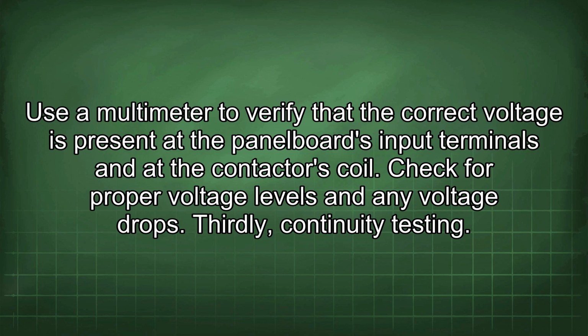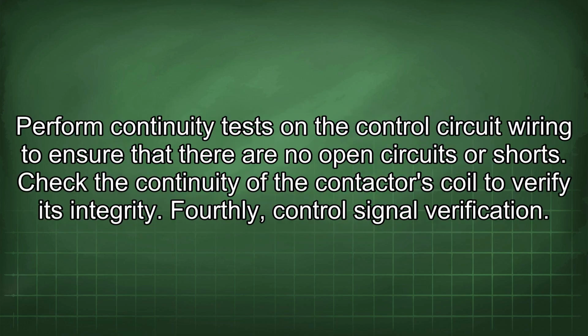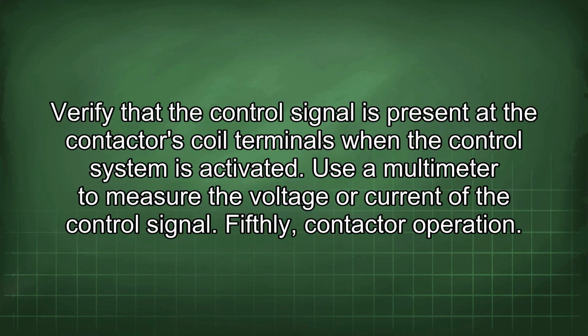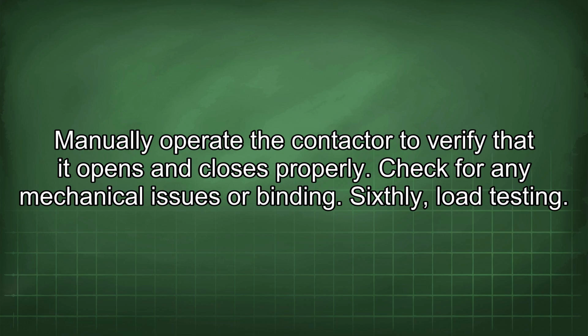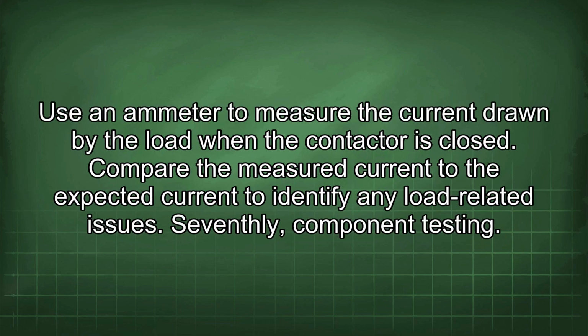Thirdly, continuity testing. Perform continuity tests on the control circuit wiring to ensure that there are no open circuits or shorts. Check the continuity of the contactor's coil to verify its integrity. Fourthly, control signal verification. Verify that the control signal is present at the contactor's coil terminals when the control system is activated. Use a multimeter to measure the voltage or current of the control signal. Fifthly, contactor operation. Manually operate the contactor to verify that it opens and closes properly. Check for any mechanical issues or binding. Sixthly, load testing. Use an ammeter to measure the current drawn by the load when the contactor is closed.